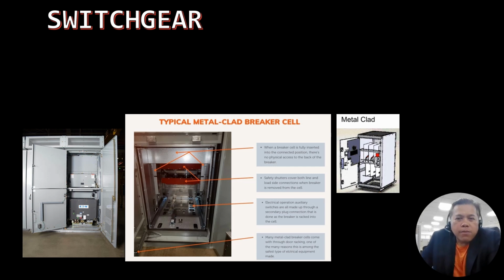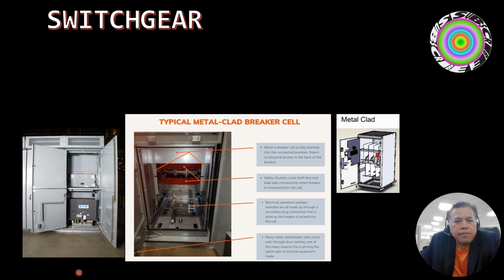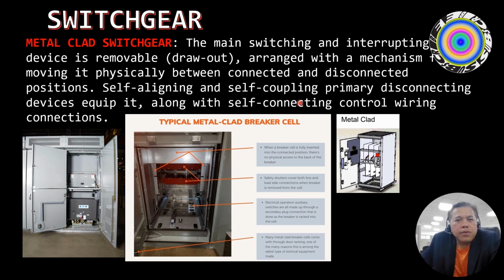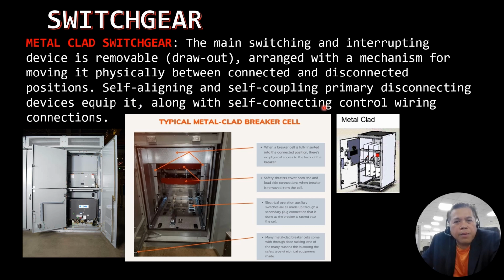Then we're talking about the switchgear. This is our switchgear, metal clad switchgear. You can see the photos here. So this is all the information. Metal clad switchgear has an interrupting device on a removable, withdrawable, draw-out mechanism, moving physically between disconnected and connected positions, with self-aligning and self-coupling primary disconnecting devices. As you can see here.